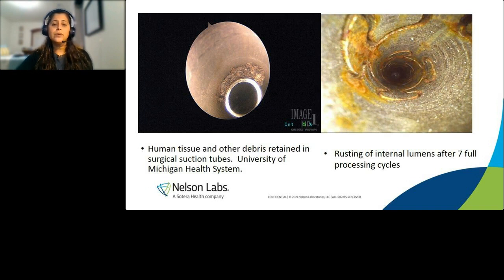But when we went with a borescope inside, because things were failing, we're like, why is this failing if it looks really good? We put a borescope in the channel, in the lumen, and this is what we found. So we took pictures and sent it to the manufacturer and said, hey, we have a problem here. If this is happening after six cycles, your device needs to be redone. It needs to go back to the drawing board, and new materials have to be used for manufacturing your product.